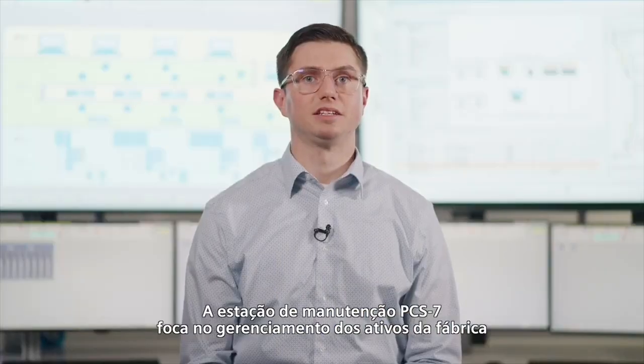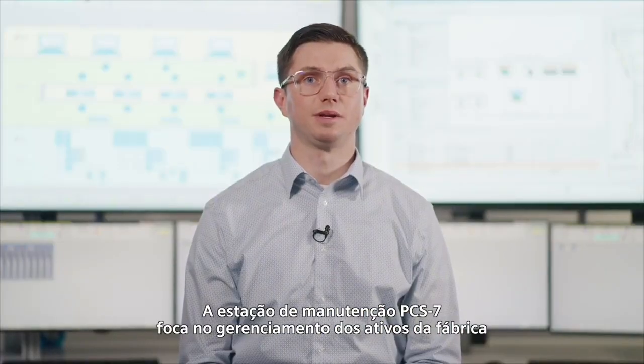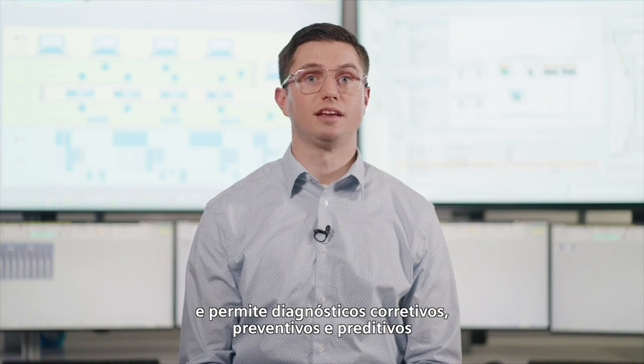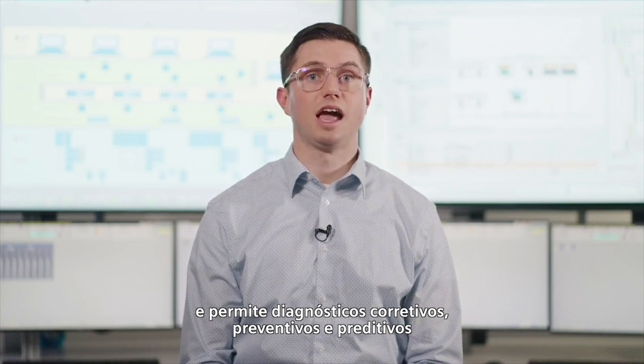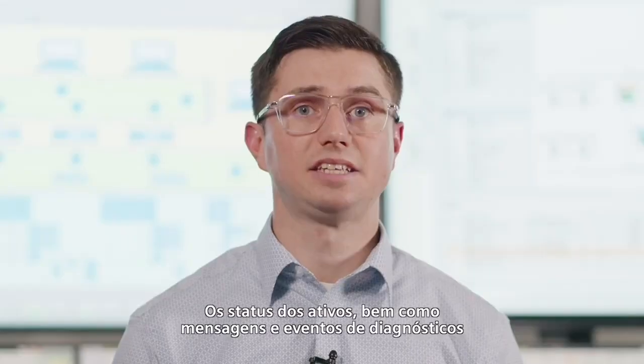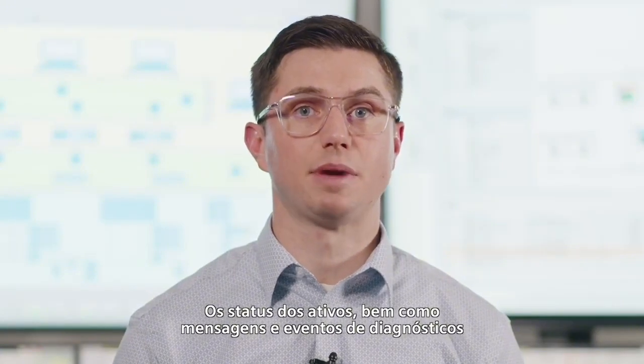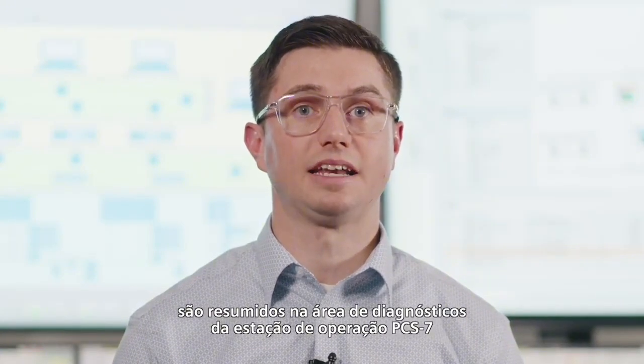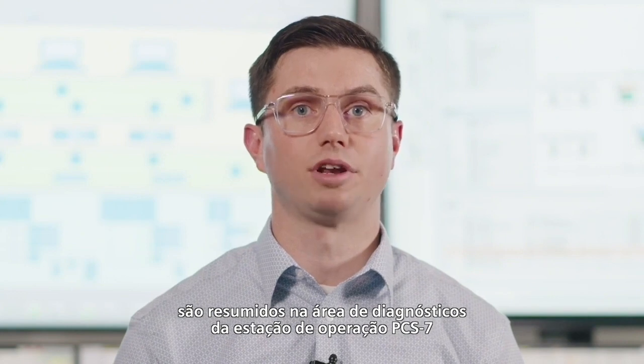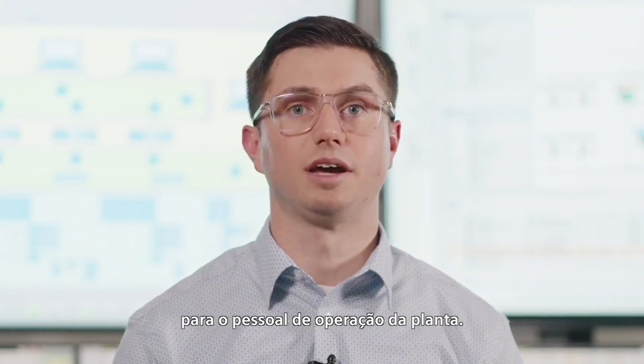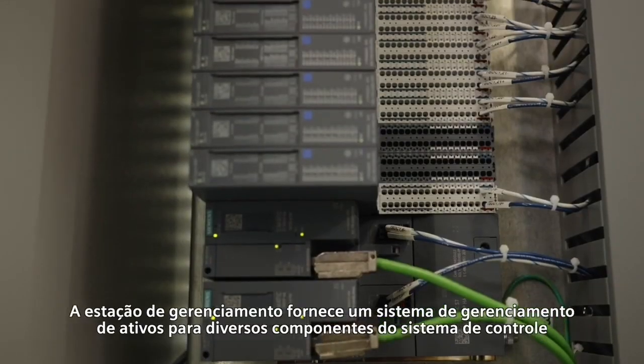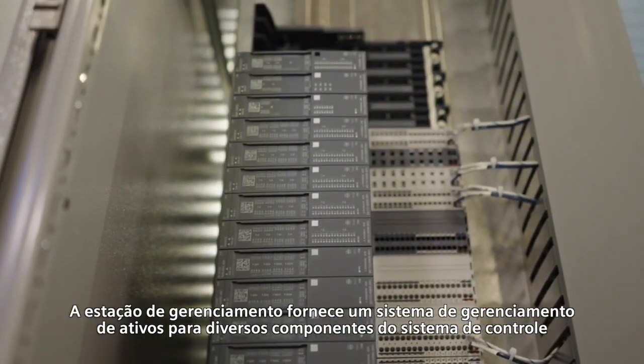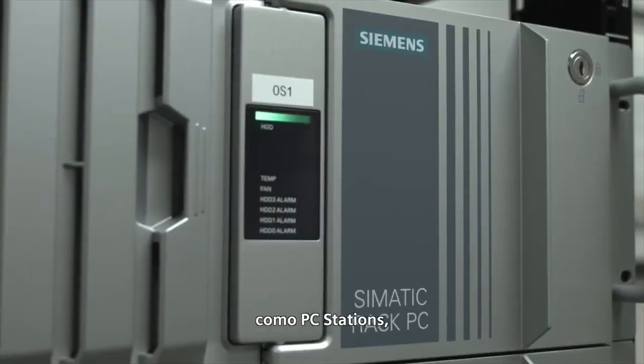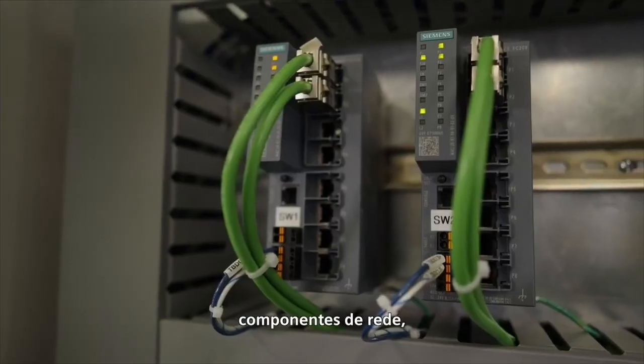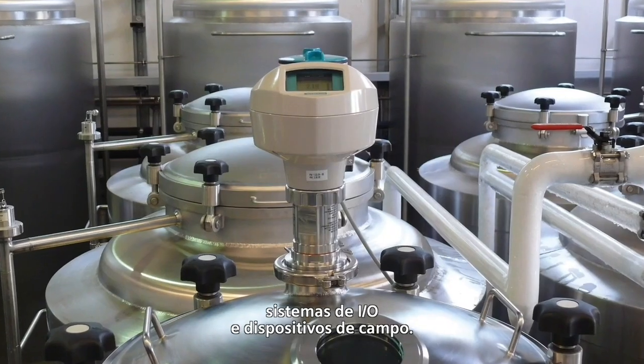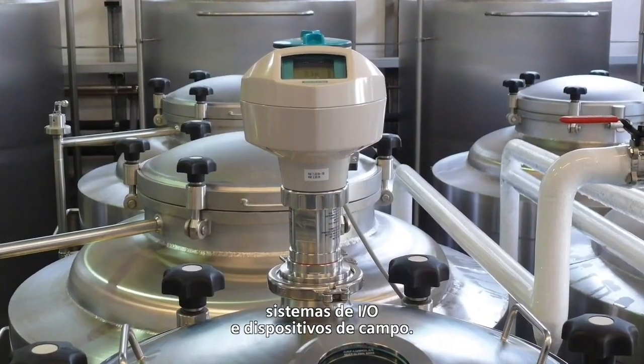The PCS7 maintenance station focuses on plant asset management and enables corrective, preventative, and predictive diagnostics, as well as maintenance of the plant. Asset statuses, as well as diagnostic messages and events, are summarized in the diagnostics area of the PCS7 operator station for the plant maintenance personnel. The maintenance station provides an asset management system for many control system components, such as PC stations, network components, controllers, I/O systems, and field devices.